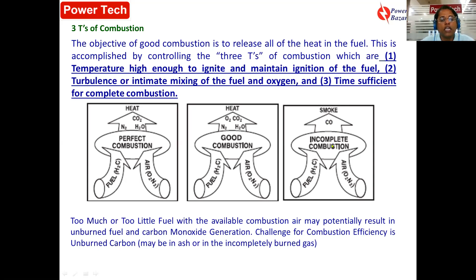But what is incomplete combustion? You are giving fuel, you are giving little amount of air, or perfect air is not there. You are not giving enough time for the fuel to burn. Time is not there, turbulence is not there, and temperature is not very high. So triple T is missing here, and you are getting CO or carbon monoxide. Therefore, too much or too little fuel with available combustion air may potentially result in unburnt fuel and carbon monoxide generation. The challenge for combustion efficiency is unburnt carbon. If you can remove unburnt carbon or carbon monoxide or unburnt in the ash or incompletely burned gas, then you will achieve good combustion efficiency.